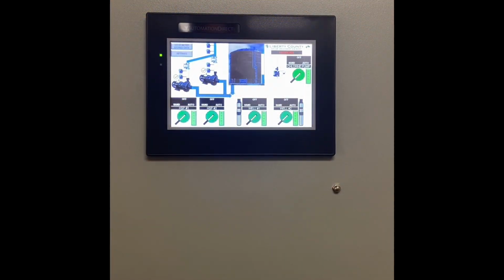Okay, we've powered the system up. You can see the screen as it's illuminated. Now, a couple things to note. I do not have any of the inputs or outputs connected to the system, so nothing will actuate. We will not get any alarms. We will not get any float actuation. We will not get any pump actuation other than putting the pump in hand. That will be it. I'm a very methodical person, so I like to move left to right, top to bottom.